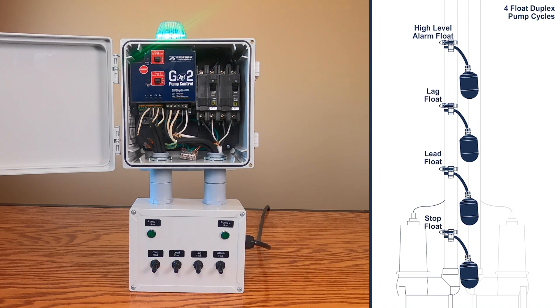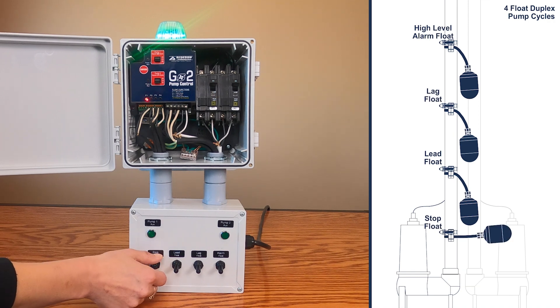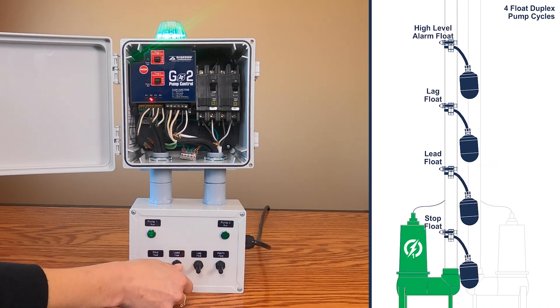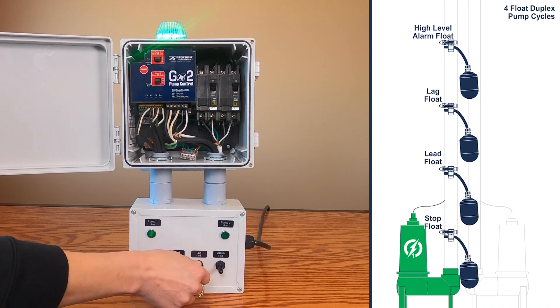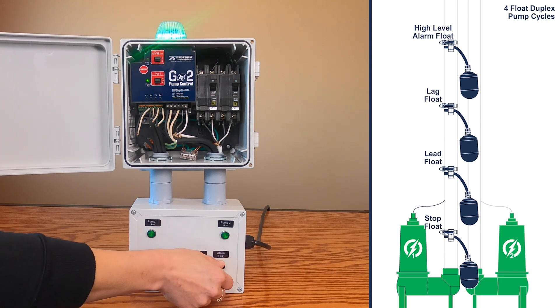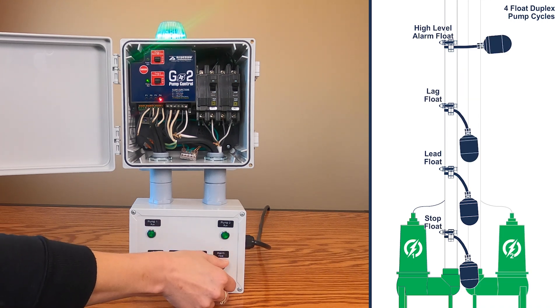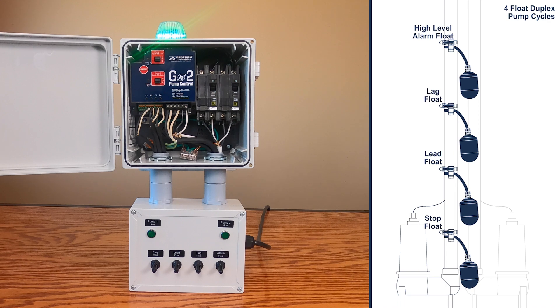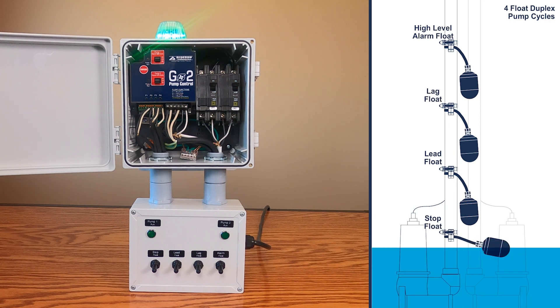Four toggle switches are used for float simulation: off, lead, lag, and high. Let's get started by simulating two pumping cycles where the lead pump will alternate after each pumping cycle. A pumping cycle is defined as when the pump turns on and when the pump turns off.